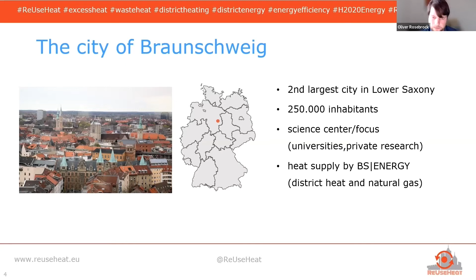Thinking about district heating in Braunschweig, the network was installed already in 1924. Most of the heat is generated in CHP plants - nearly everything that goes into the district heating network is covered by CHP plants. We have a total of roughly 250 kilometers of district heating grid in the core, so one large district heating network and several decentralized grids, most with temperatures above 100 degrees C in the supply flow.